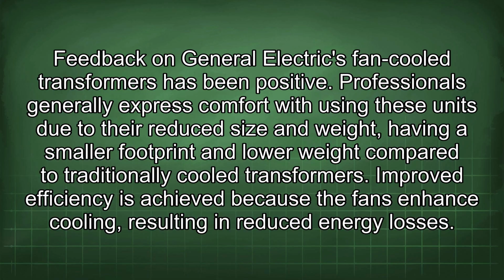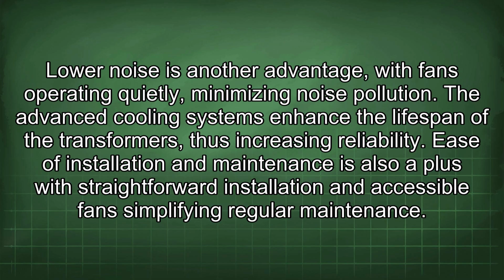Professionals generally express comfort with using these units due to their reduced size and weight, having a smaller footprint and lower weight compared to traditionally cooled transformers. Improved efficiency is achieved because the fans enhance cooling, resulting in reduced energy losses. Lower noise is another advantage, with fans operating quietly, minimizing noise pollution. The advanced cooling systems enhance the lifespan of the transformers, thus increasing reliability. Ease of installation and maintenance is also a plus, with straightforward installation and accessible fans simplifying regular maintenance.